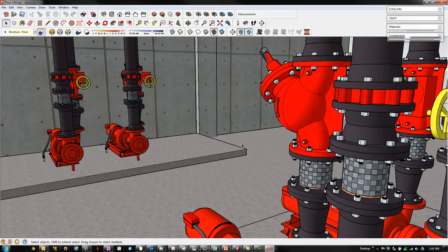The problem is that on more than one occasion, I've actually seen check valves, which is what that is. Actually, it's a triple duty valve. There's a check valve built into it along with a throttling valve and a service valve, which we'll talk about briefly here in a minute. But bottom line is I've seen them put in backwards. So it's a good indicator, but it's not as absolute an indicator as what I'm about to show you.